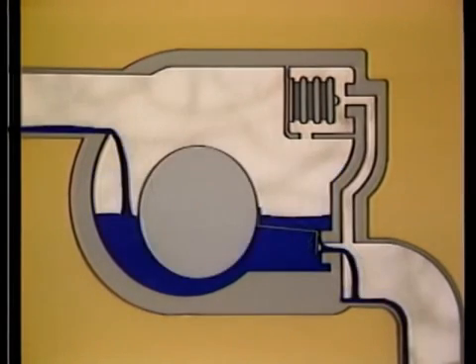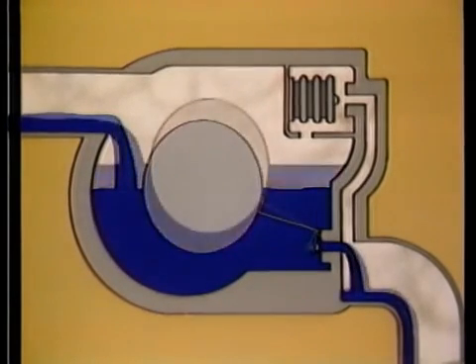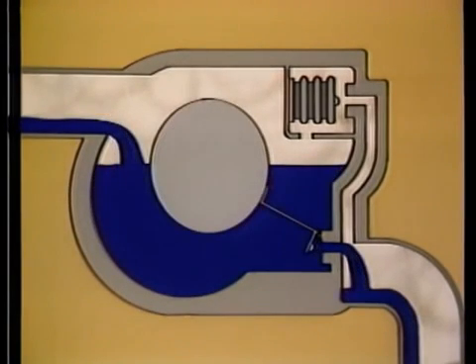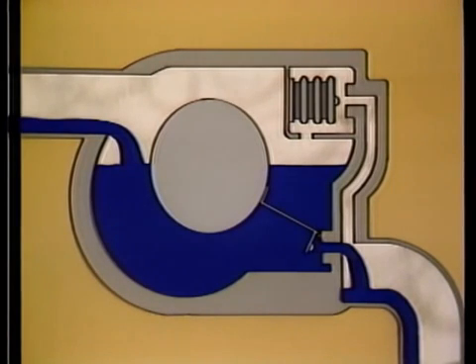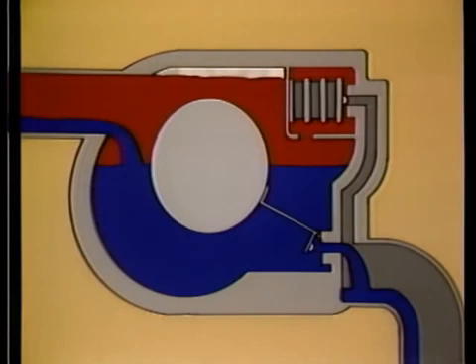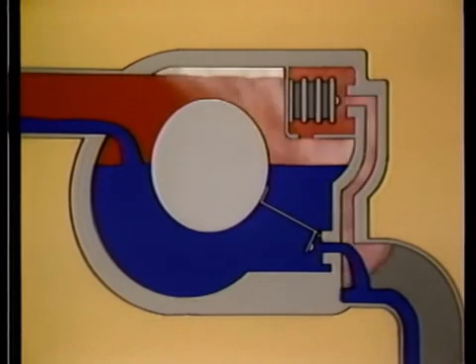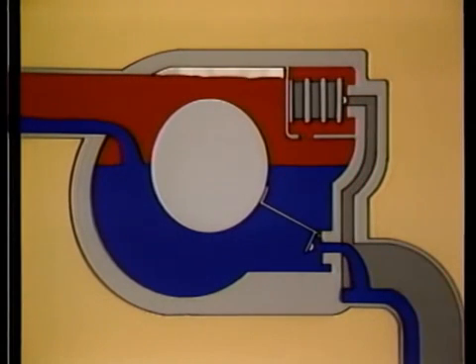The condensate level in the trap lowers and raises the float height, thus modulating the discharge flow. When steam reaches the trap, it collects above the condensate level and heats the thermostatic element, closing its valve. Hereafter, the thermostatic valve will open intermittently to vent mixtures of non-condensibles and steam.